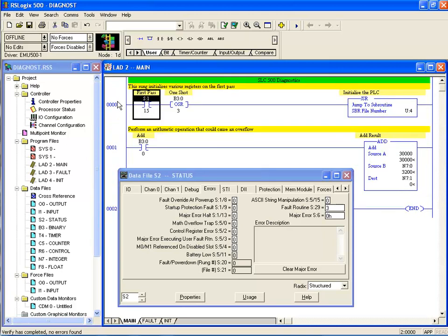We also have the first pass bit, another very handy feature in diagnostics or setting up the PLC perhaps, and that will send you to a program file that will initialize your PLC on startup. So there's a rung here, rung 0 in this PLC, the first rung of the program. This first pass bit is true for the first scan of the PLC when it's put into run.